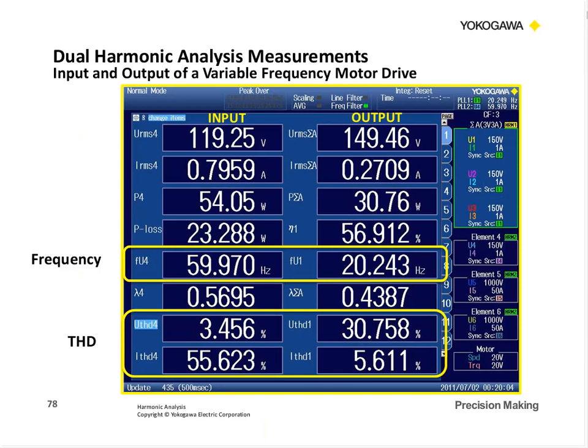Here's some examples of our dual harmonic analysis. We look at the two frequencies. This is almost 60 hertz and 20 hertz on the drive. And we can look at the total harmonic distortion of the voltage and the current. And here is the total harmonic distortion of that PWM voltage and THD of the current. So we get all these simultaneously, input and output together.